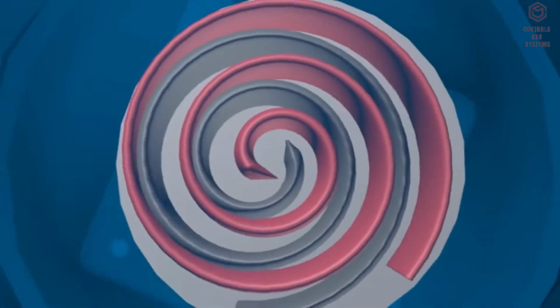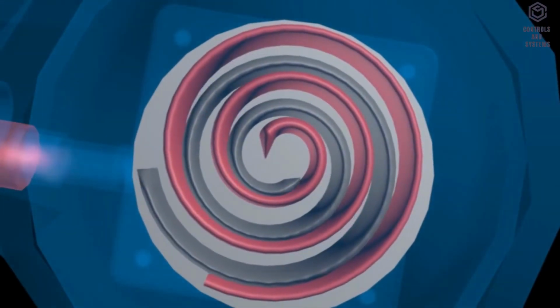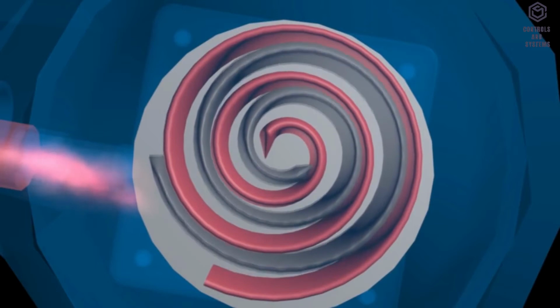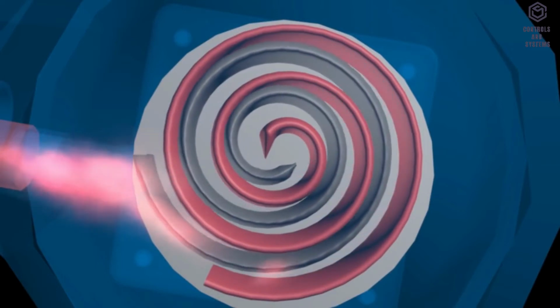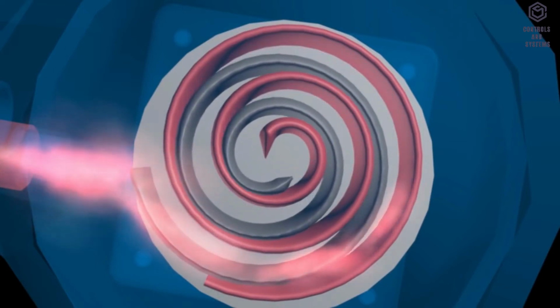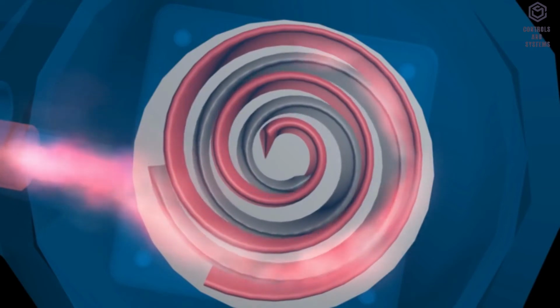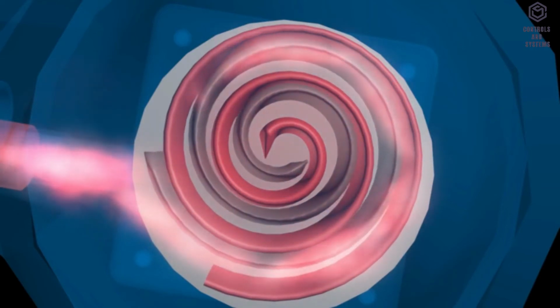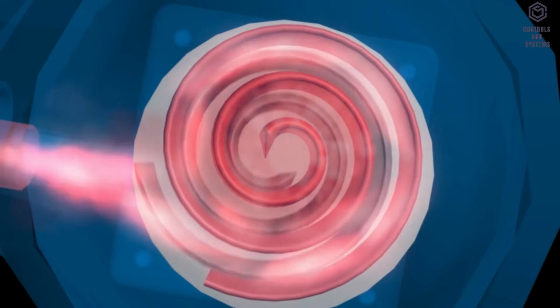The scroll compressor works as follows: gas at low pressure and temperature enters the suction line and goes into the compressor. The low pressure and temperature gas is pressurized by the scroll compressor into high pressure and temperature gas. The high pressure and temperature gas then goes through the discharge line and into the condenser.